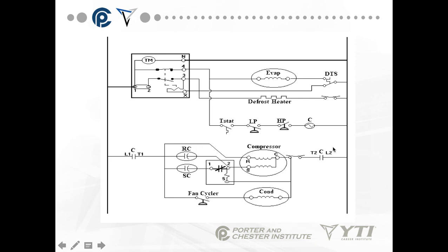This is a commercial diagram with an electric defrost heater, and we have a defrost limit here. Whenever I have an electric defrost heater, I have to have a limit switch. Fan cycling occurs in a low ambient control, so this is called a low ambient control.